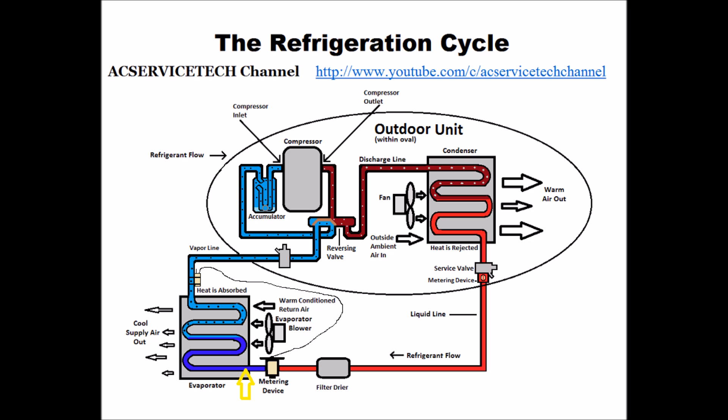It then starts to absorb heat from the house. It continues to absorb heat until it turns into a saturated state where liquid and vapor both exist. That's where it's able to store most of the heat it's absorbing from the house during that phase change from liquid to vapor. It then turns into a complete vapor and continues to absorb heat until it comes out of the evaporator coil.